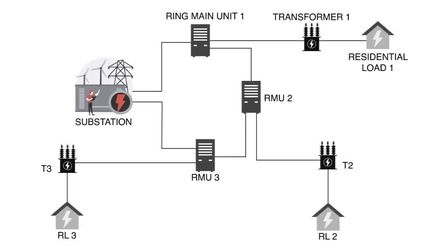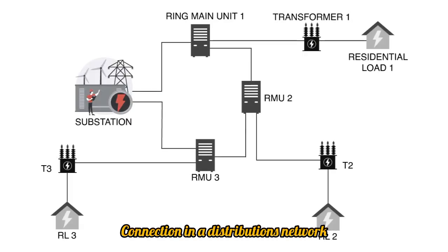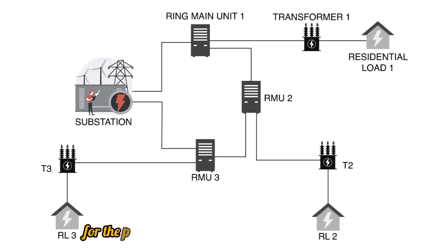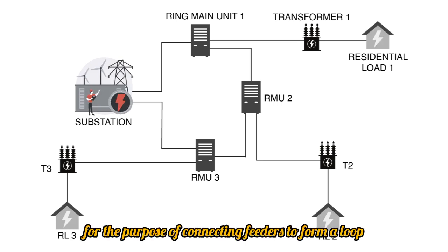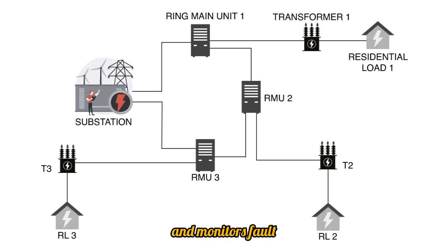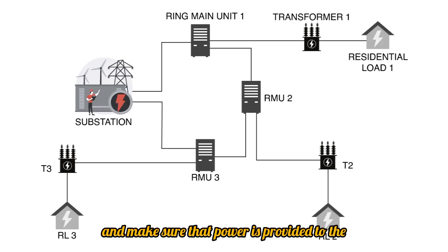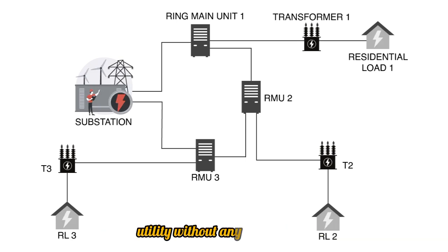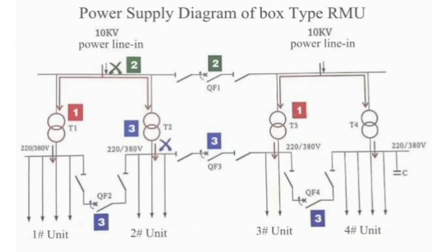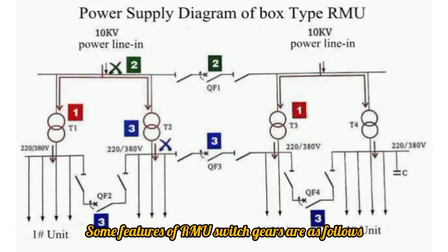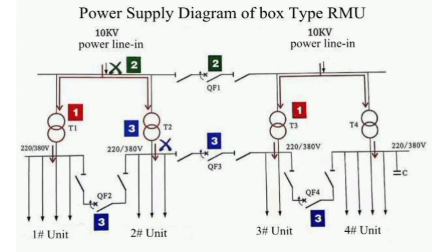Ring main unit connection in a distribution network. Ring main units are used in a ring main network for the purpose of connecting feeders to form a loop and monitoring faults or any malfunction at feeders and distribution transformer end, and make sure that power is provided to the utility without any disturbance and with least possible voltage drop. Features: some features of RMU switchgears are as follows.